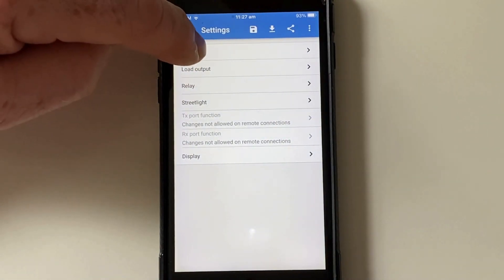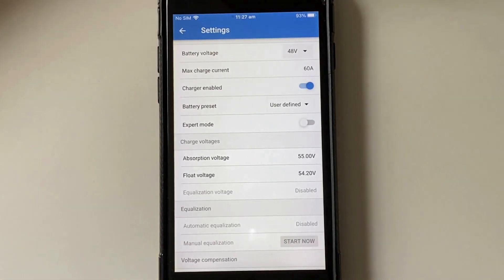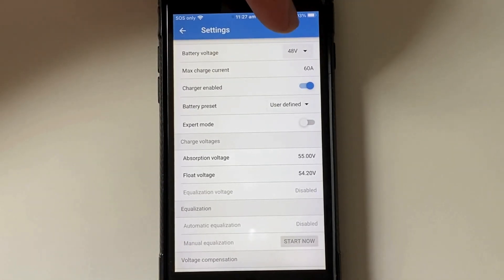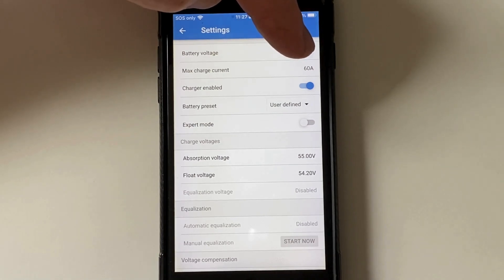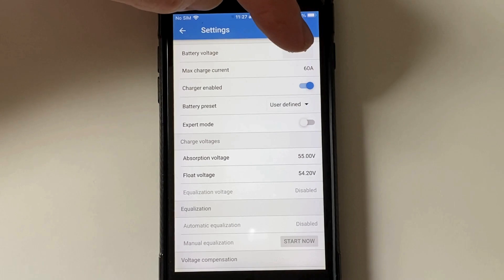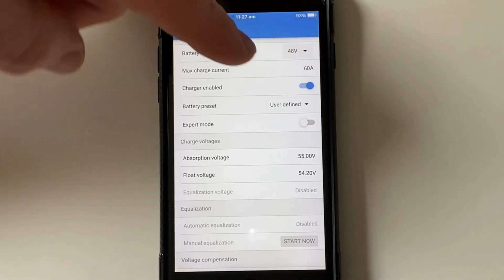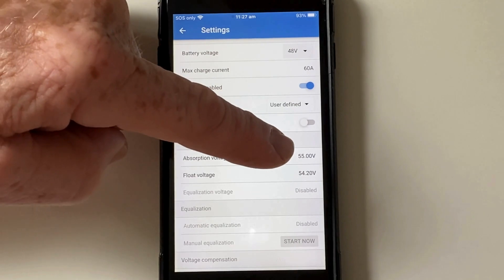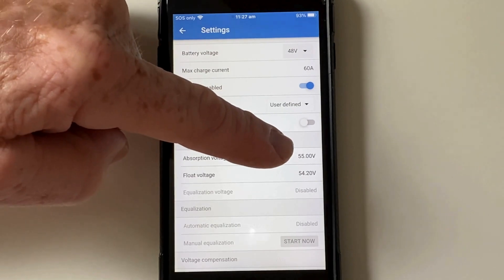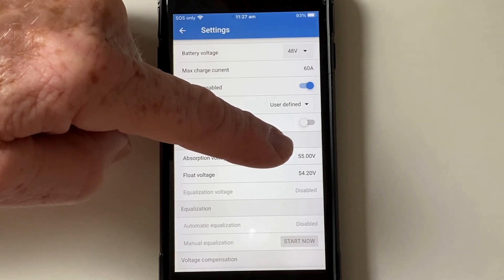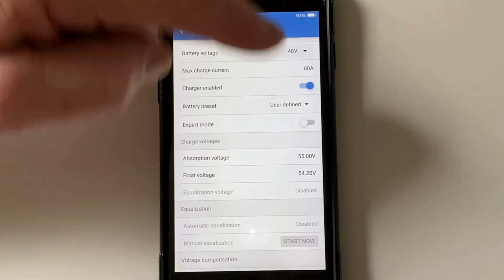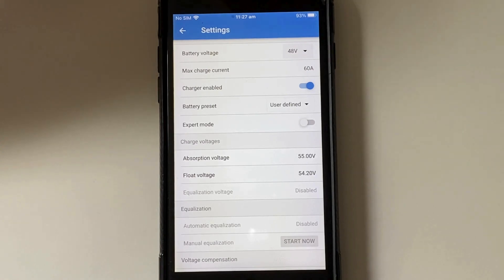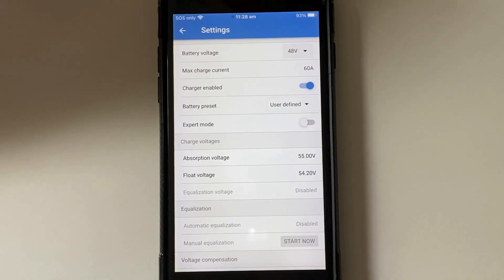Go to battery. So it's a 48 volt system. I've got it set to the max charge current. I control my current limit in the console. I'll show you that in a little while. 55 volts is all I charge to. That's all you need really for a 48 volt system. It's charging quick enough with that high voltage without compromising battery with cell degradation by overcharging.